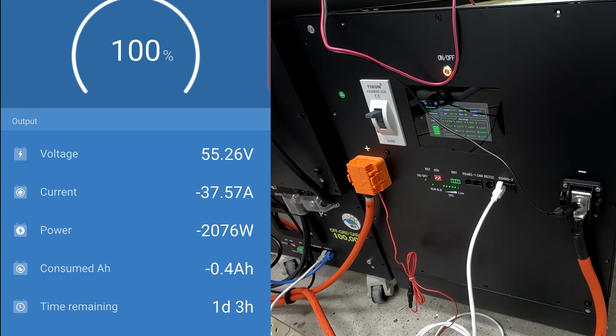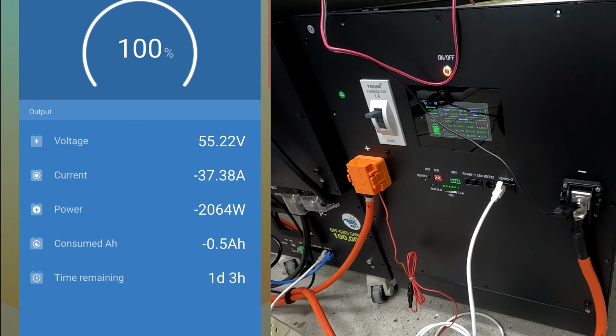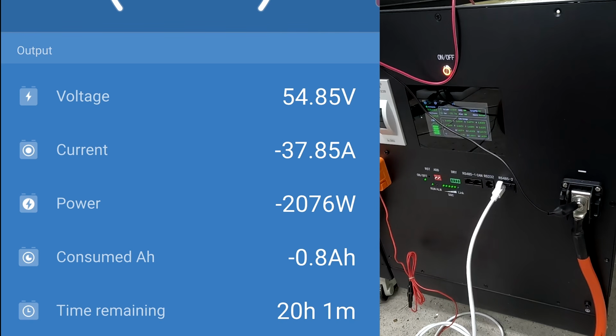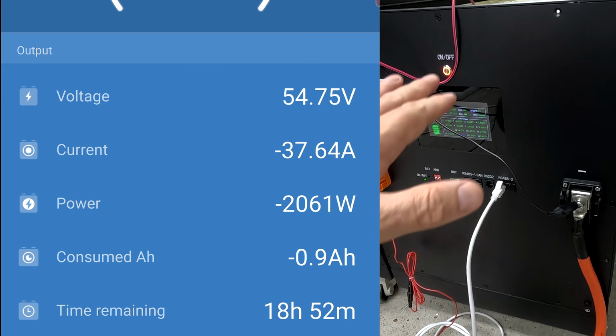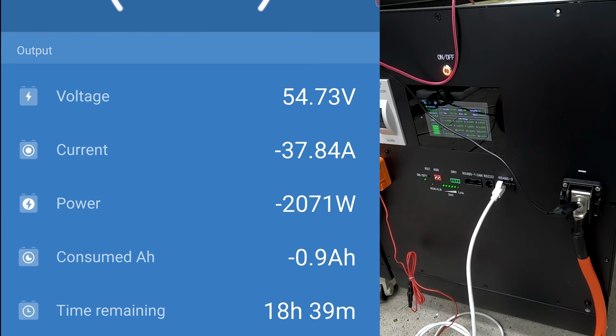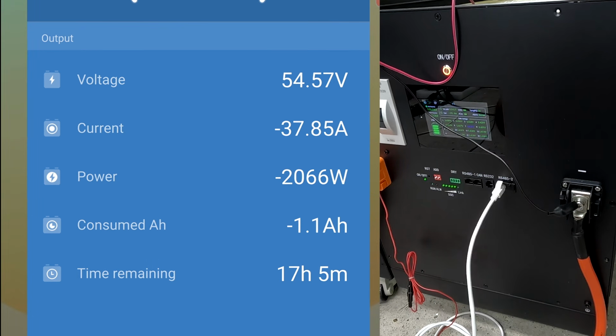It changes the calculations after a moment, so hopefully it goes down to about 10 to 12 hours. The remaining time is coming down now, thankfully. We're discharging with 2 kilowatts, 37 amps. This will increase after a while because the voltage of the battery will lower, and since we're still discharging with 2 kilowatts, the current will increase. So we should see about 42, 43, 44 amps at some stage. 38 now - see, it's increasing slightly.